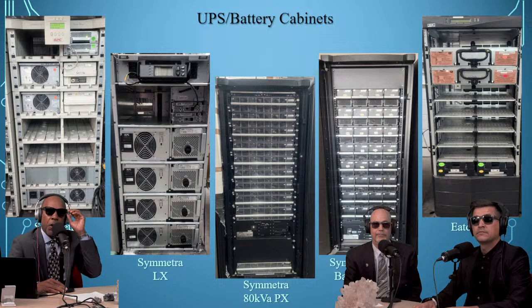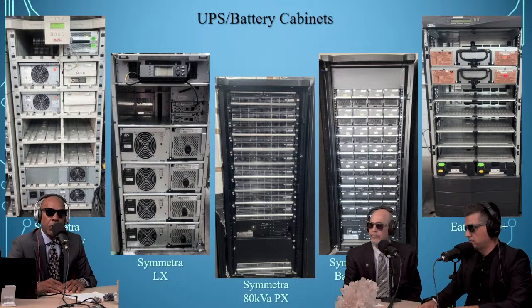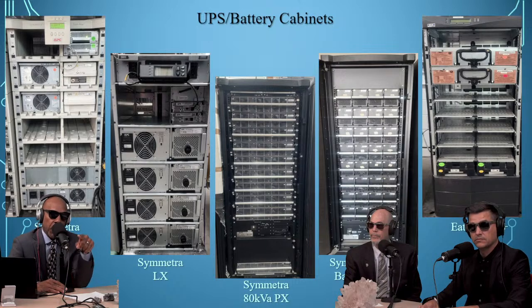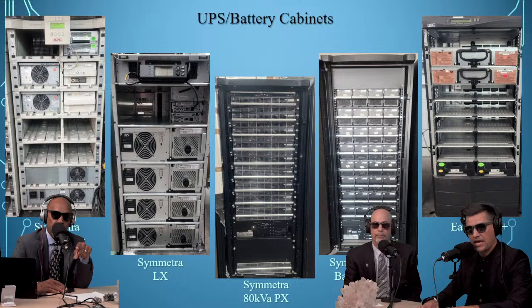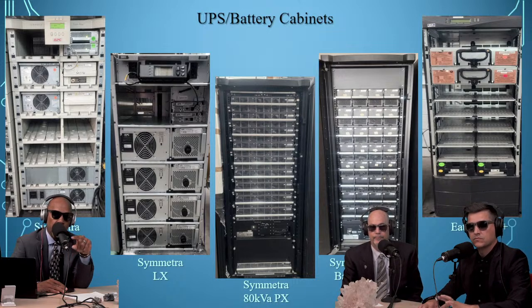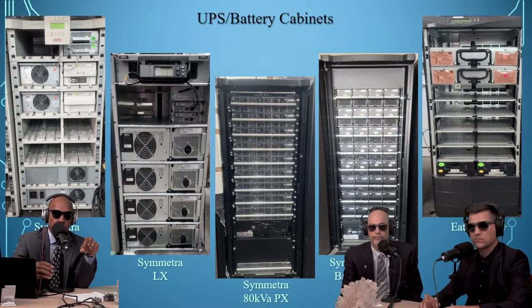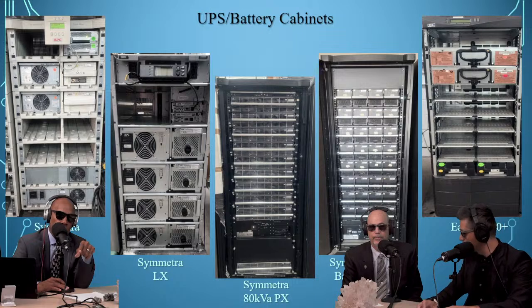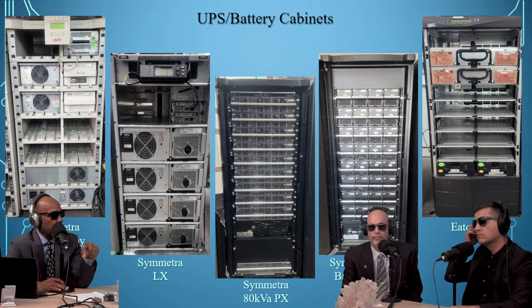Tell them what a string is. Let's look at the battery cabinet connected to the PX, the 80 kVA one. That's an external battery cabinet. You see 8 rows — in this particular configuration, a string is considered 4 of the modules horizontally. So you may think, why aren't the other ones considered part of the string? There's actually 8 strings in this battery cabinet based on the way they're wired and connected.